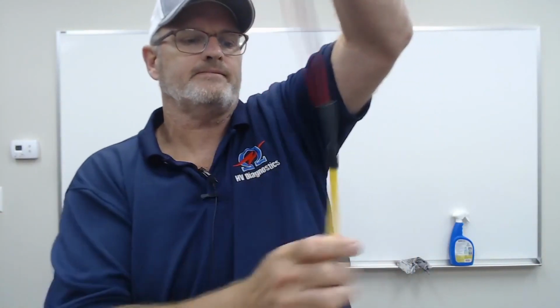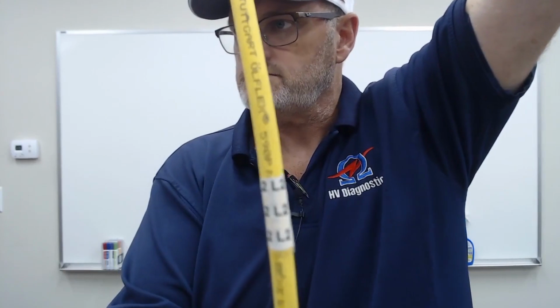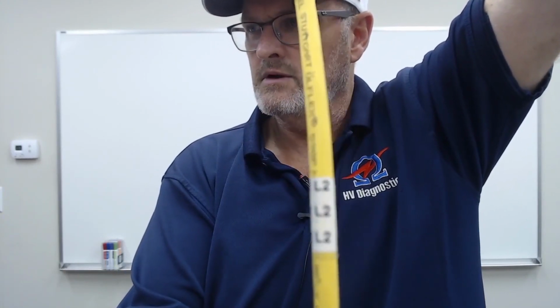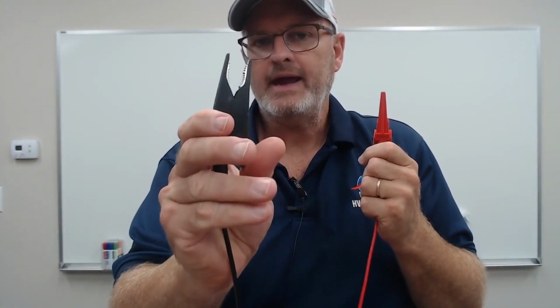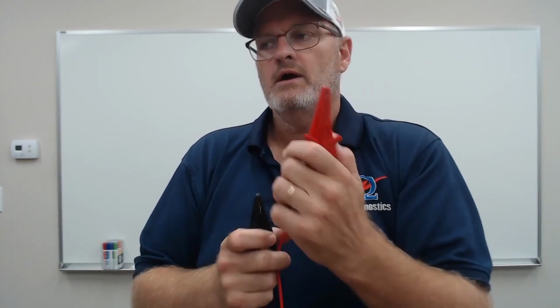Likewise, if we're doing a 3-phase cable, you can see over here, this will say phase 2, look there. The red cable will go onto B phase, and again, the black cable will go onto C phase. So you're going to have 2 cables on C phase, and you're going to have 1 cable on B phase, this one over here, and then the other cable will go to A phase.